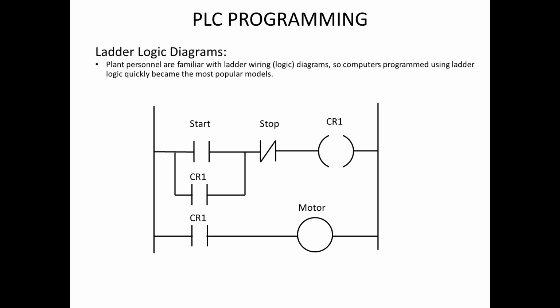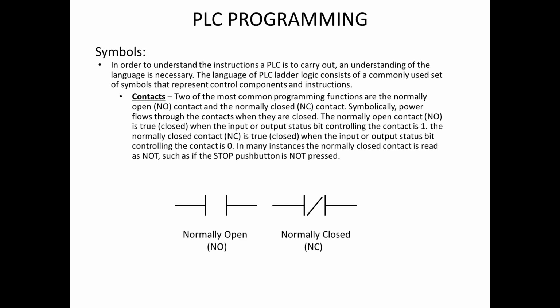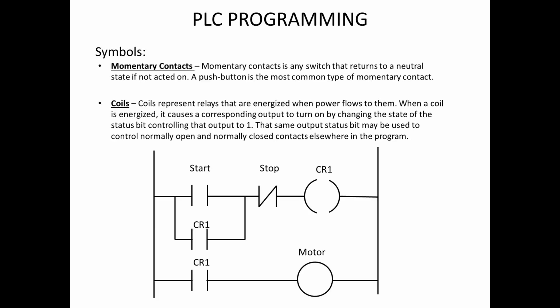They used ladder logic because the plant personnel were familiar with ladder logic, and it allowed them to understand how to program because the ladder logic diagrams were very similar to the wiring diagrams. And so with PLC programming, contacts are one of the most common programming functions. And we talked about them being normally open or normally closed, and that's usually how they are written, as the one on the left shows normally open. The one on the right with the line going through it, that's the symbol for a normally closed contact.